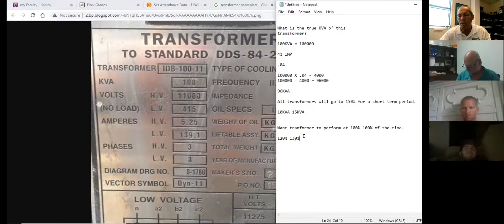Well, what happens when it's summertime and it's 103 degrees outside? What's the transformer going to do? Is the transformer going to go to 120%? Maybe 130%? Will it overheat? It'll go to 120 and 130%, but we can go to overload, up to 150%, for a short-term period. That's okay.